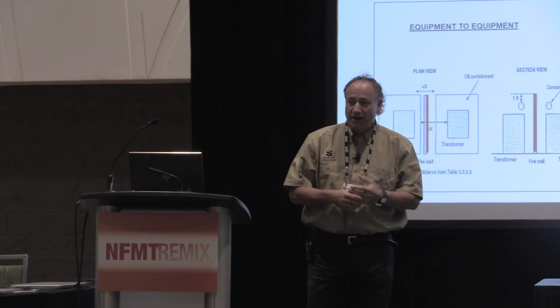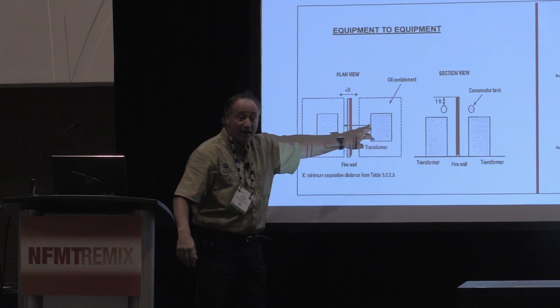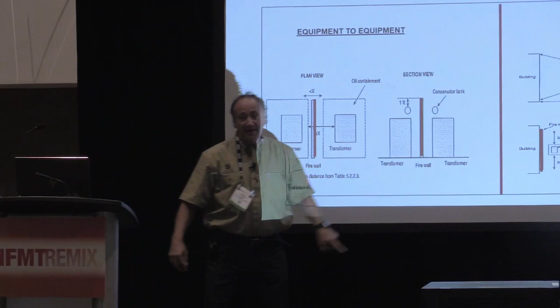Obviously, if the transformer is further or closer away, the wall could be bigger or smaller, okay? It has to protect from explosion, so we use what's called line of sight. We simply just look at the explosion line and put a barrier, a catcher's mitt, in the way. So when we're protecting transformer to transformer - which is almost as important because typically one's a spare and one's a primary - we know how big and how tall to make the barrier.